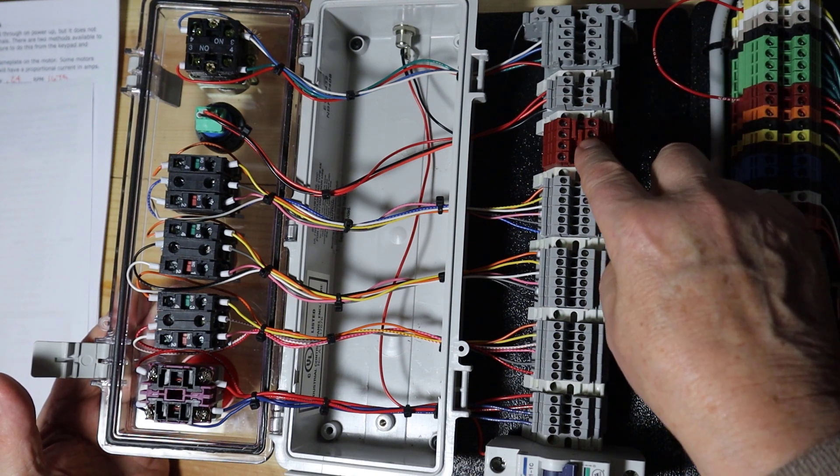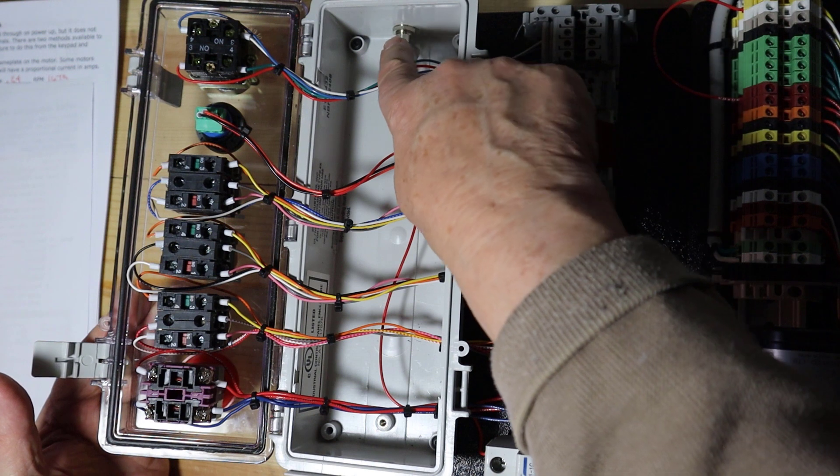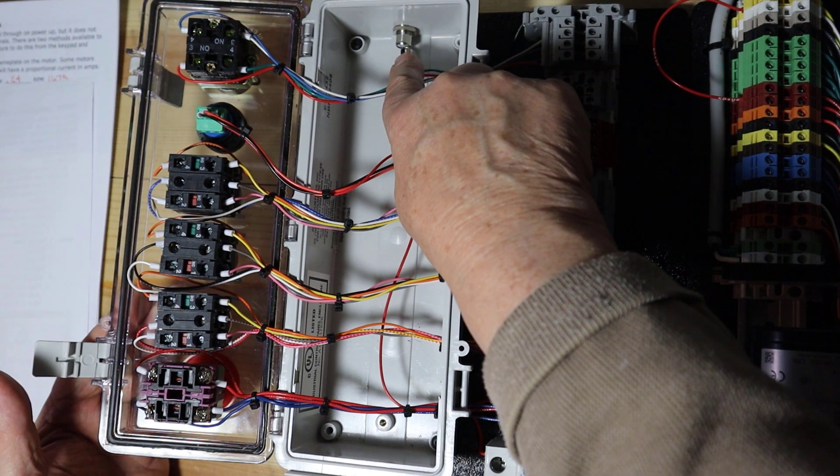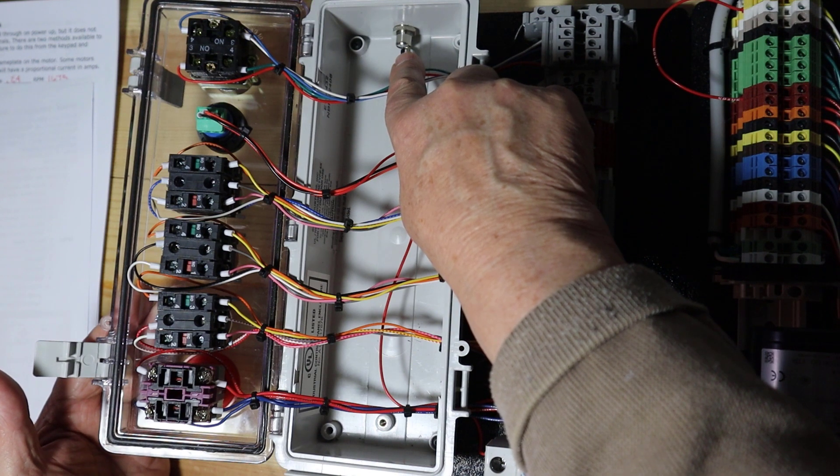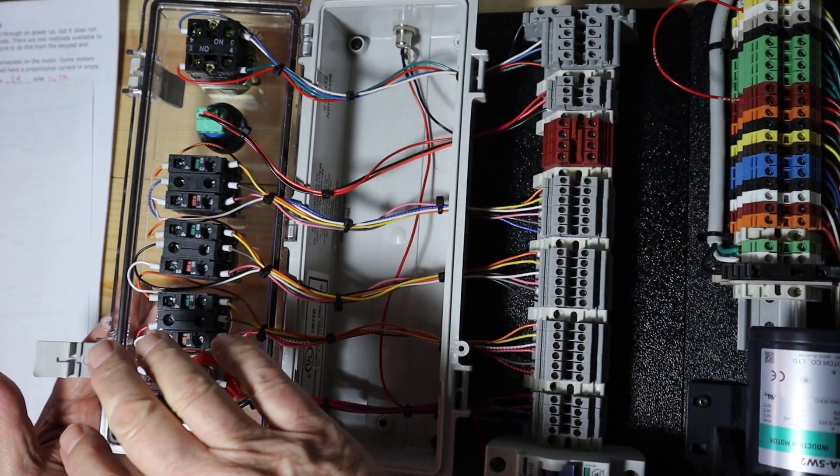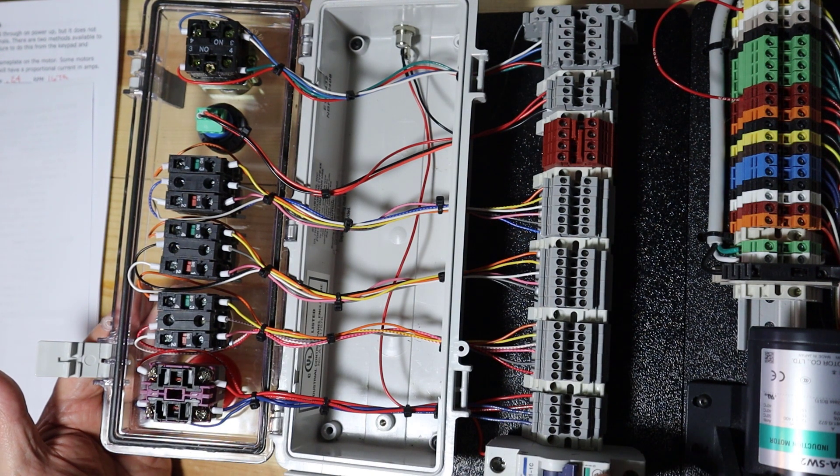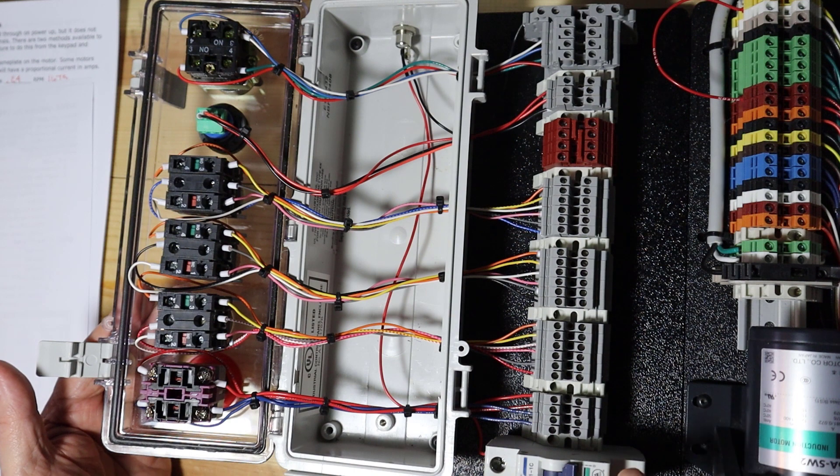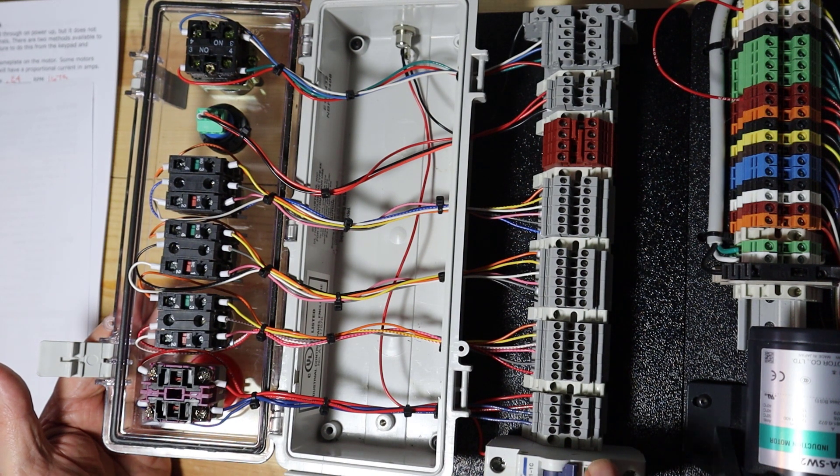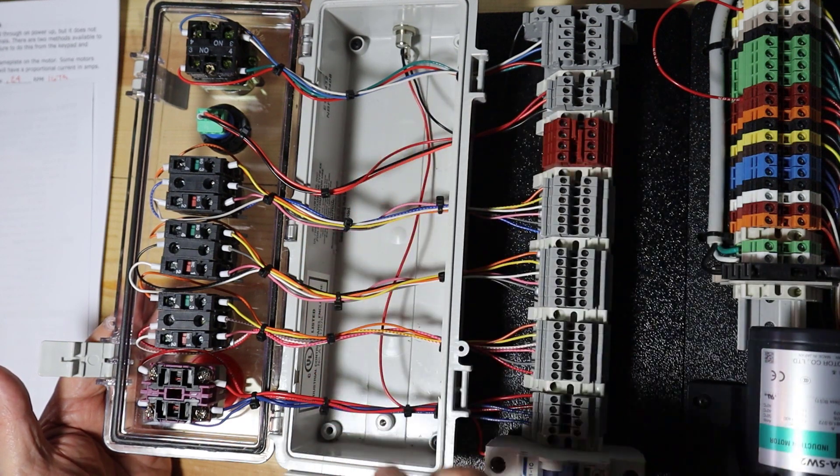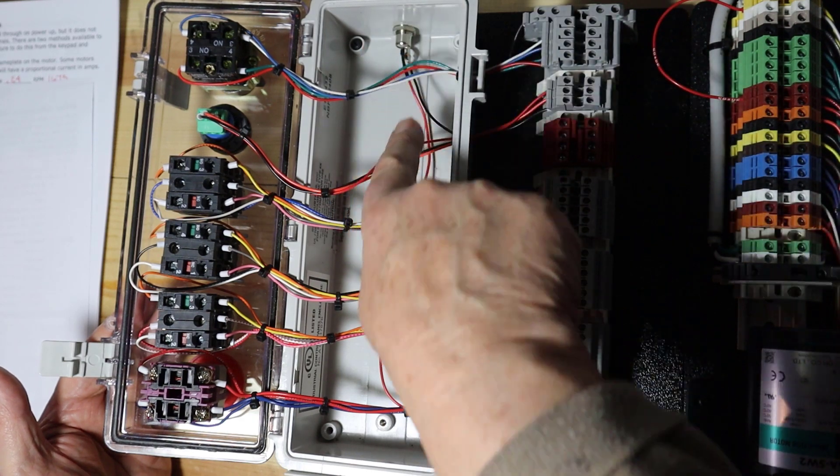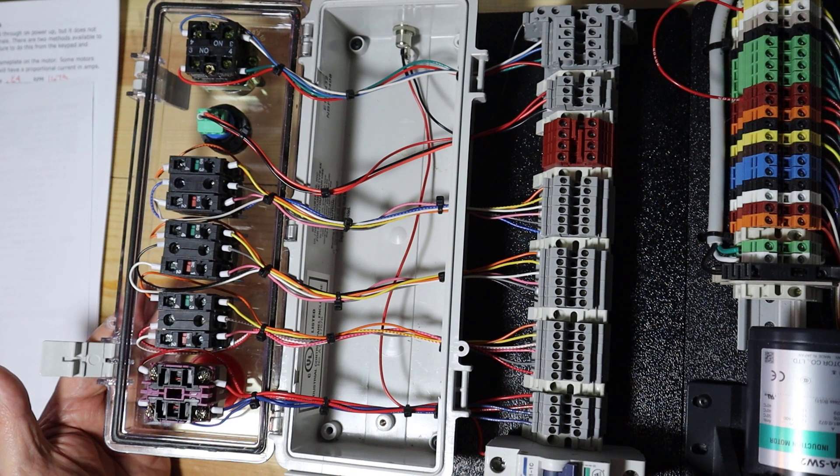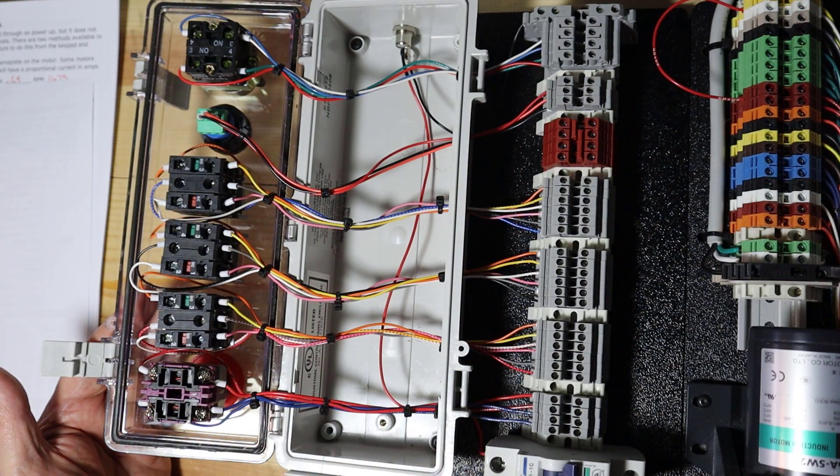These are spares to bring in power if we need it. Notice also that we have a power connector at the top of this box. That's if we want to plug in a 24 volt DC supply to make these inputs to a PLC. We can also bring in 24 volts DC down here. There's a circuit breaker right here that we can bring in 24 volts and that is the red wire running up here.